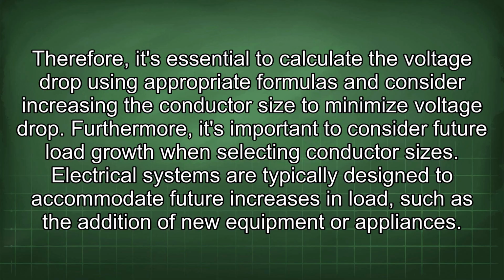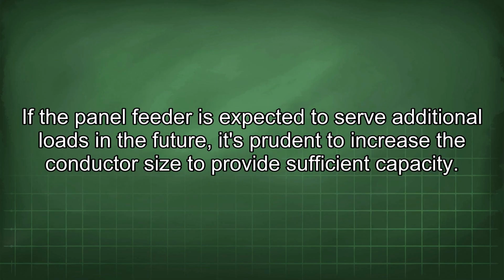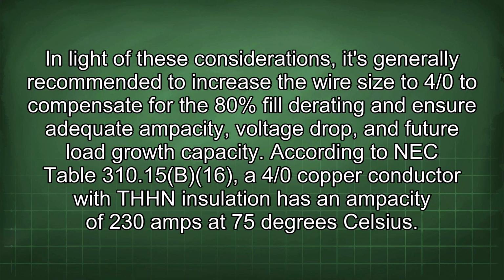Furthermore, it's important to consider future load growth when selecting conductor sizes. Electrical systems are typically designed to accommodate future increases in load, such as the addition of new equipment or appliances. If the panel feeder is expected to serve additional loads in the future, it's prudent to increase the conductor size to provide sufficient capacity. In light of these considerations, it's generally recommended to increase the wire size to 4/0 to compensate for the 80% fill derating and ensure adequate ampacity, voltage drop, and future load growth capacity.